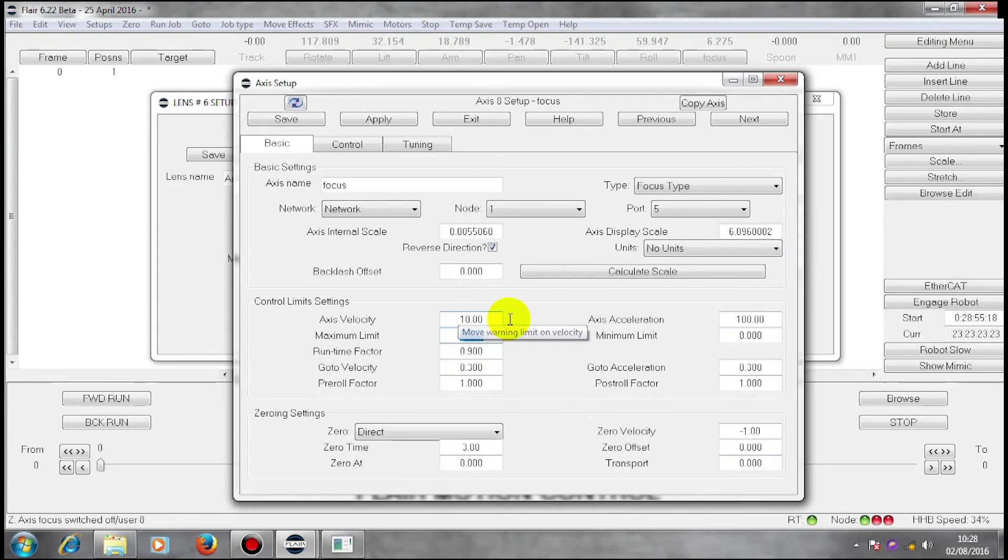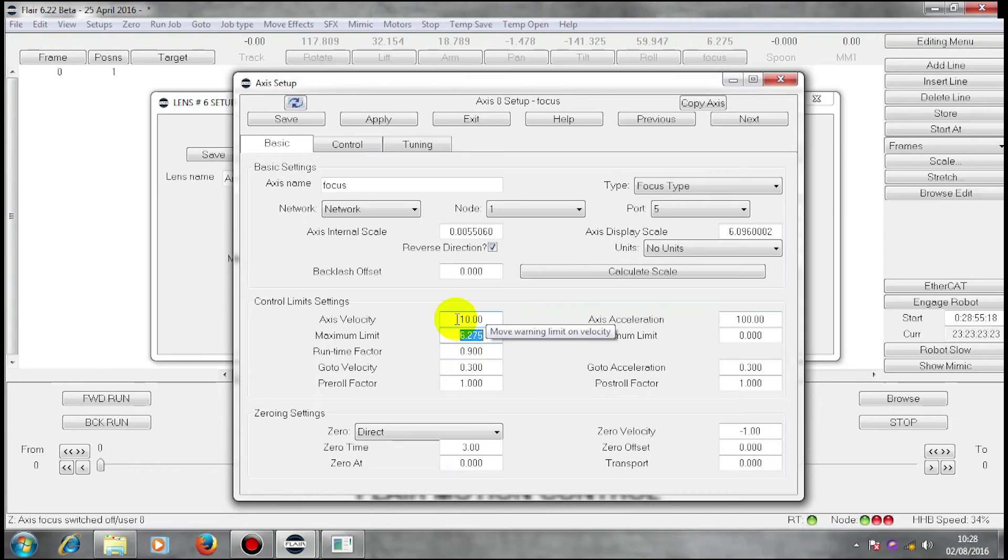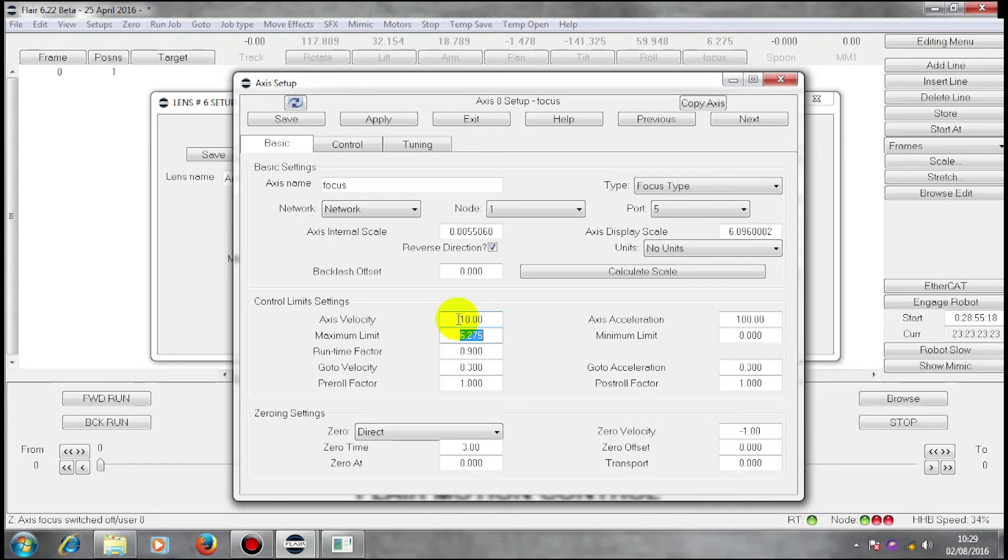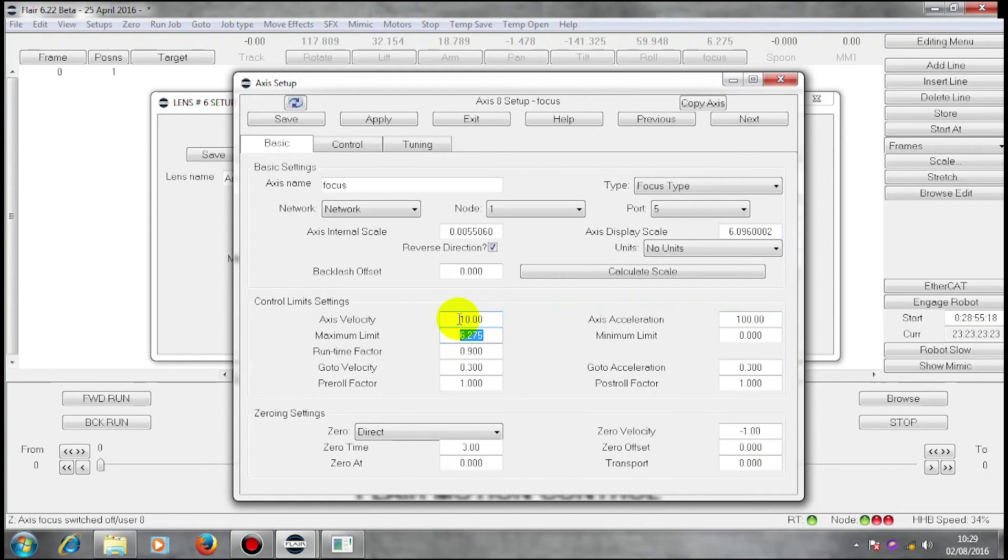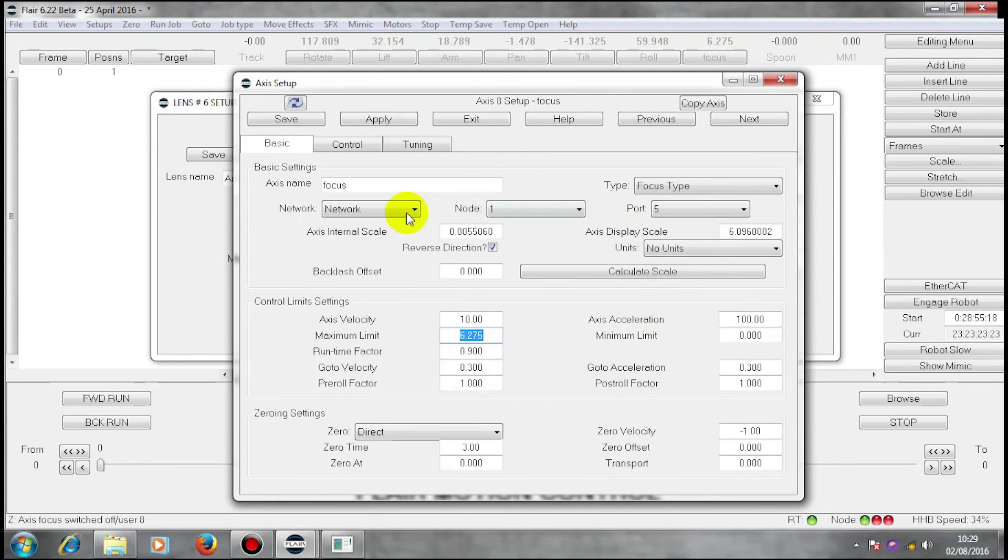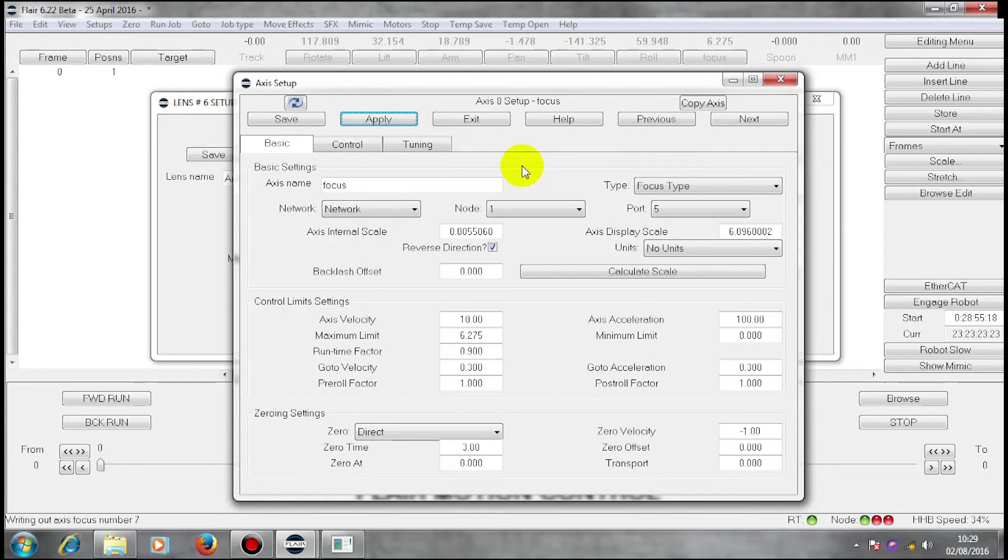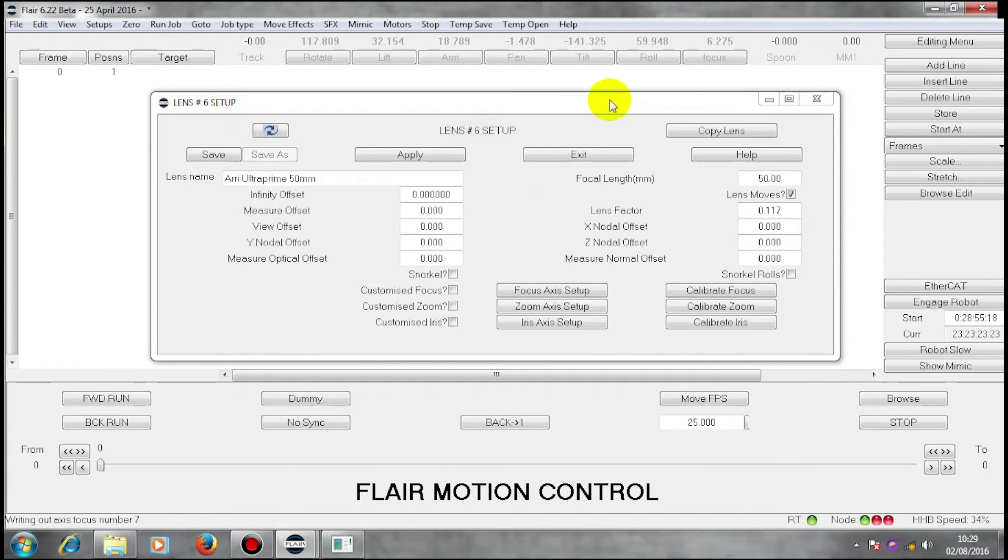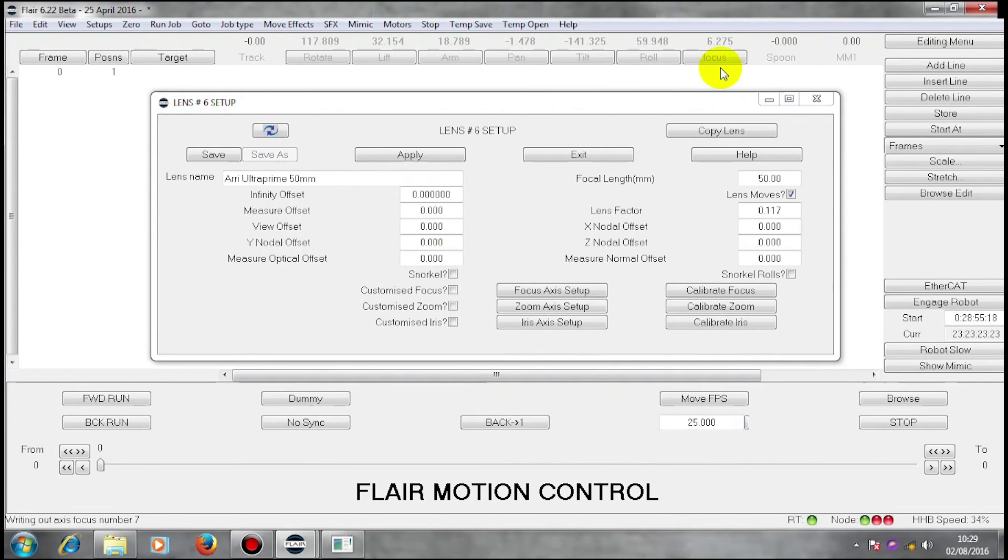And I have an axis velocity and an axis acceleration. These values are arbitrarily chosen in order to allow me to move my lens. If I had a very stiff or sticky lens, I might need to reduce these. But this value shows that I believe I can go from one end of the lens to the other with this motor in 0.6 of a second, which is a reasonable figure for a bolt. So with these changes having been done, I'm going to save, apply that lens. That lens setup motor position wise is now done.